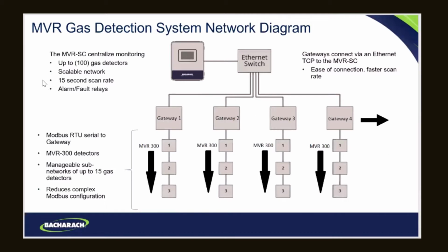The scan time is typically about 15 seconds, depending on how many of these things are on the network. And what the controller is going to do is it's going to go out as a Modbus master, and it will go to each one of these gas detectors in sequence and poll them to see if anything has changed. If nothing has changed, that means everything's great. It moves on to the next one, and it repeats the sequence. If it detects anything along the way, it will respond as configured.